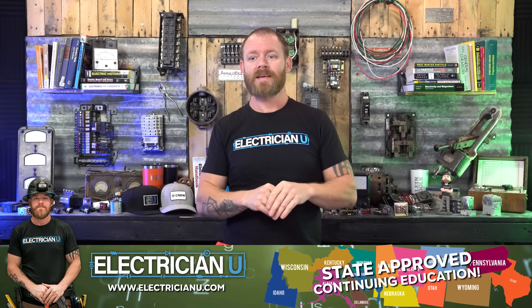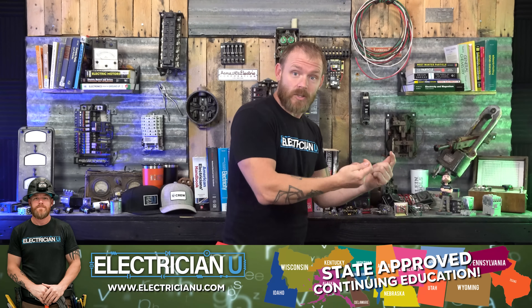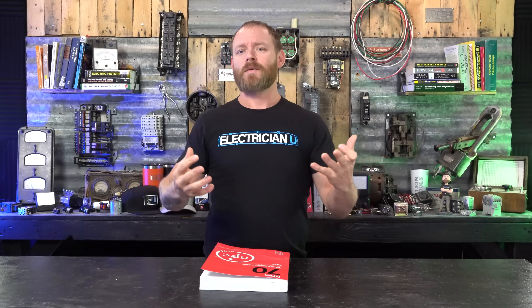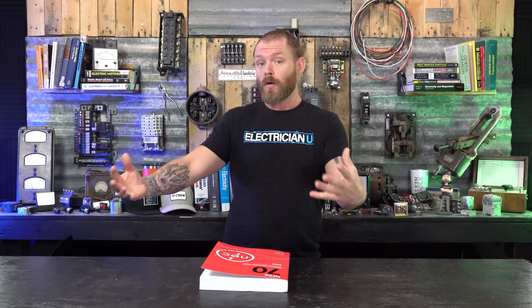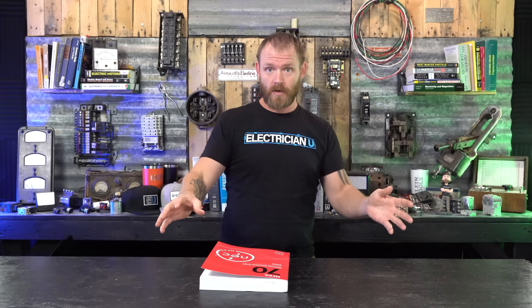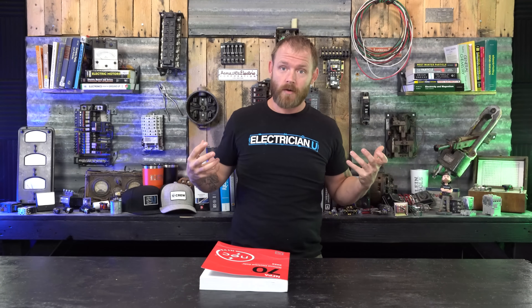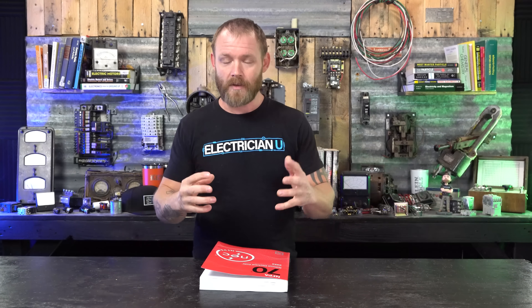There's not a whole lot of places that have to have dual function breakers, and honestly if you just wanted to put all arc fault breakers in a panel and then go put GFCI devices everywhere, you can do that. But a lot of places they're not smart to have a GFCI. In a kitchen we have to put arc fault protection — the entire kitchen has to be arc faulted — but behind a refrigerator you're not going to put a GFCI device, because if it trips you have to pull the whole refrigerator out and your food could go bad.